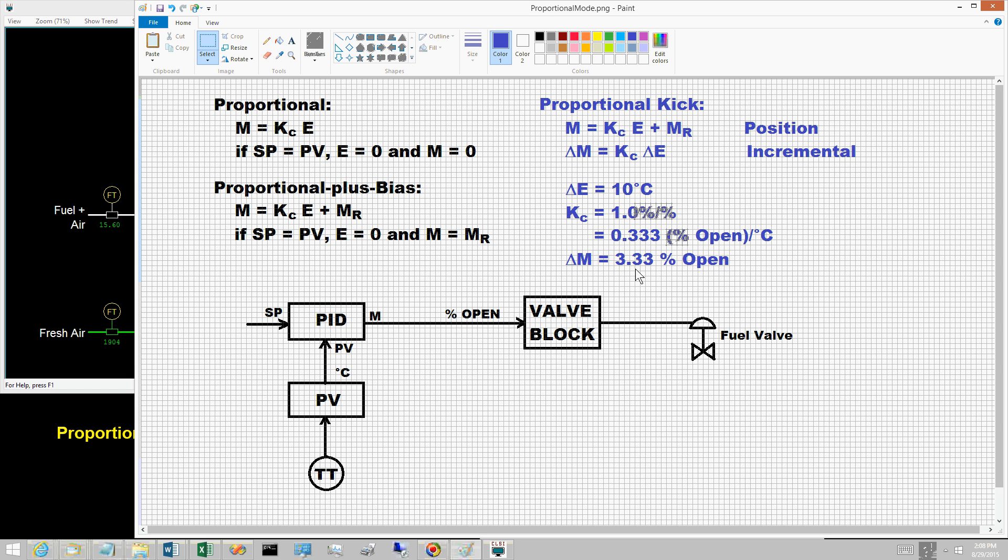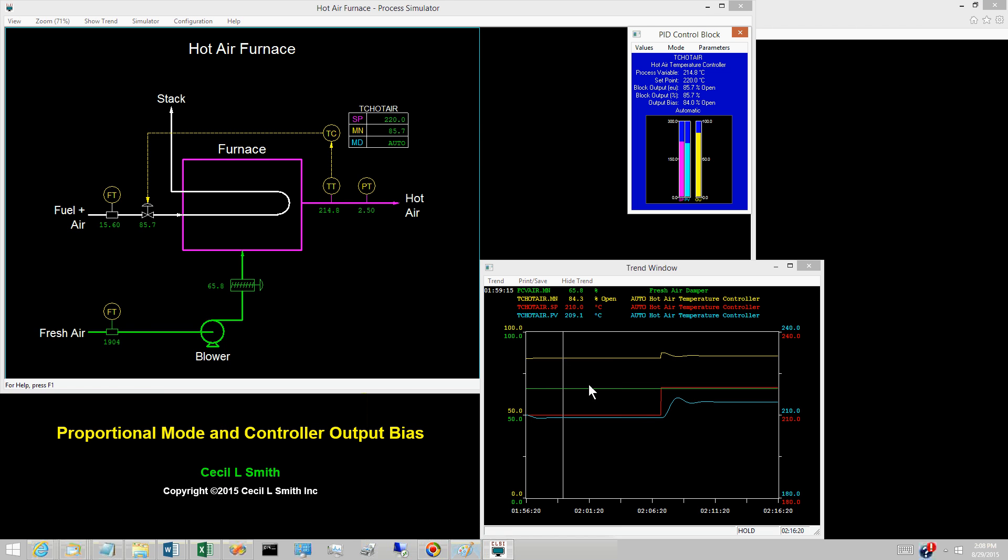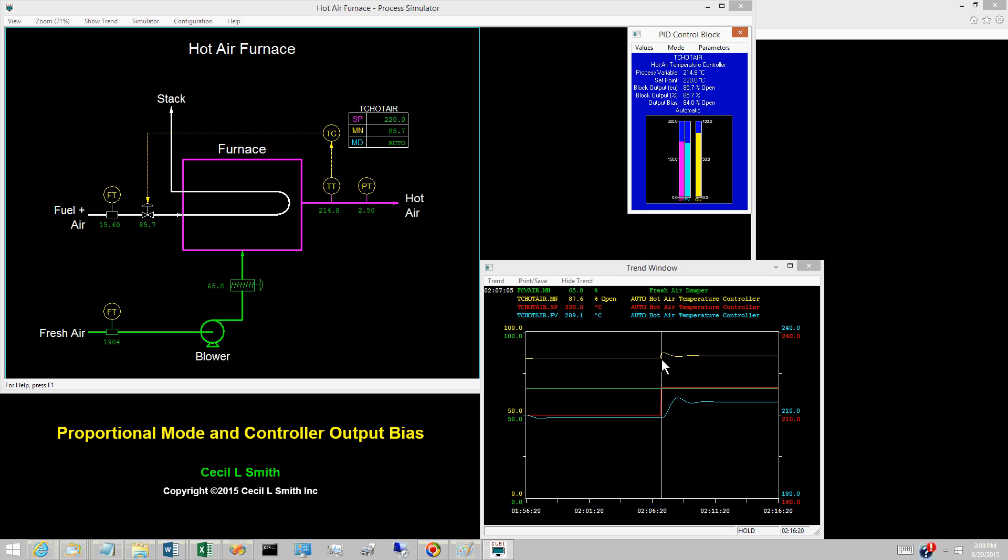The set point change of 10 degrees Celsius causes the proportional mode to abruptly change the controller output by 3.33% open. The controller output changes from 84.3% open to 87.6% open at the instant the set point changes.